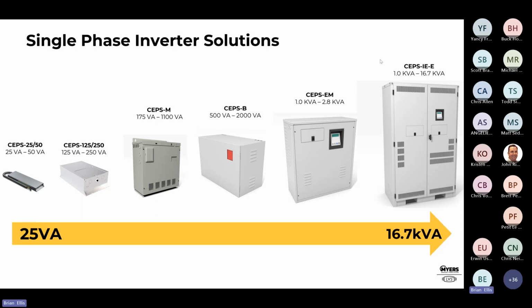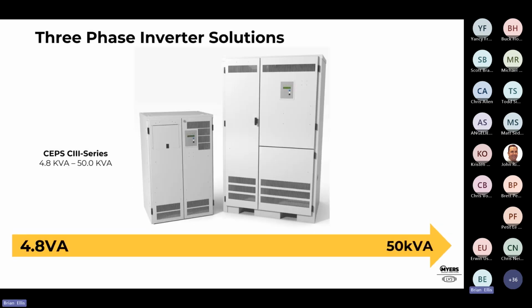And then we have the 1 kVA to 16.7, which is the IE or E series that is available for you guys. One thing to note: inverters typically have a single switched input on the smaller units, meaning you can bypass one zone. But as you step up to larger wattages, you're going to be controlling more than one lighting control zone, in which case, most of the time, you're not able to do a switched input. Those would then require the bypass relays that we're going to talk about later. Let's go to the three-phase.